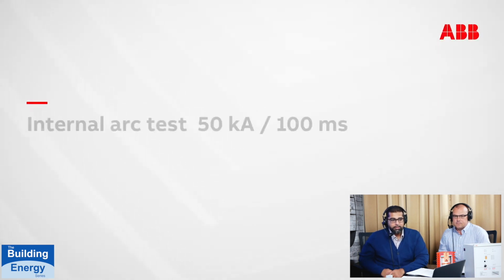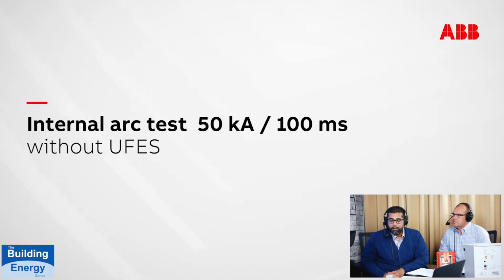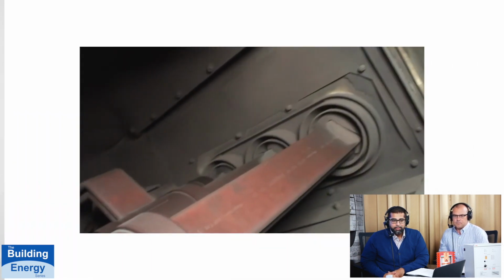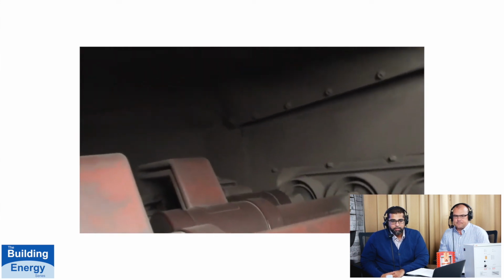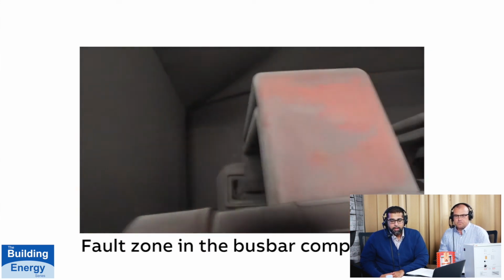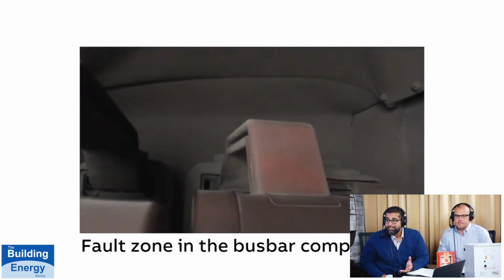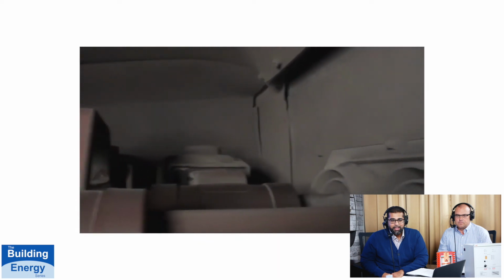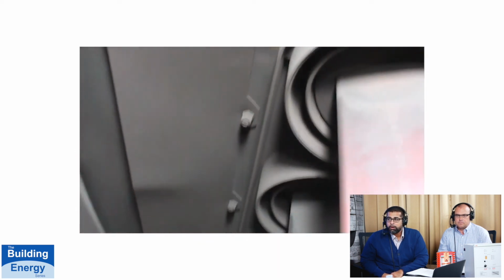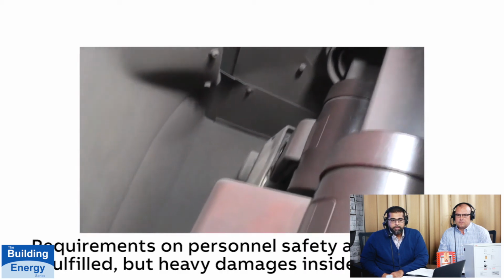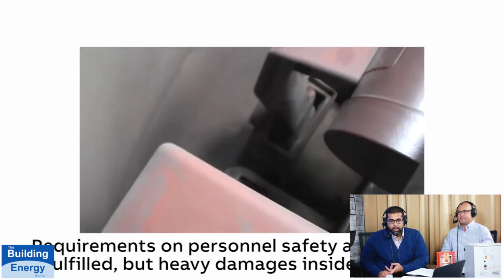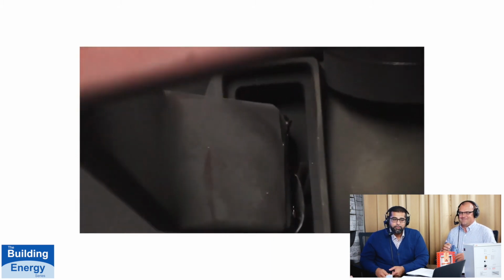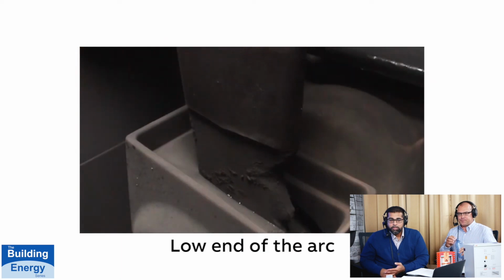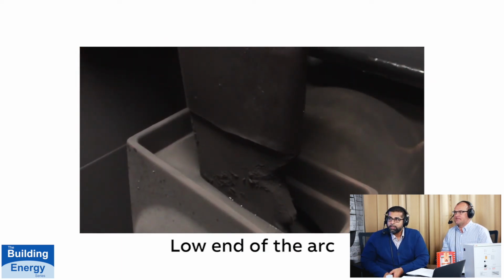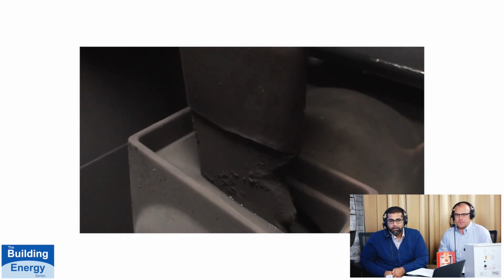So the first is the equipment without the UFES. Doesn't look good, the amount of destruction that has taken place. You see there's a lot of carbon buildup, and this has happened in a tenth of a second. For all intents and purposes, this gear is no longer usable. So the customer, whoever has this installed, has to replace it. They have to deal with the lead time, the cost, the installation, the engineering that goes into this type of upgrade. And this is custom gear, generally speaking, so you're looking at a year's worth of lead time.